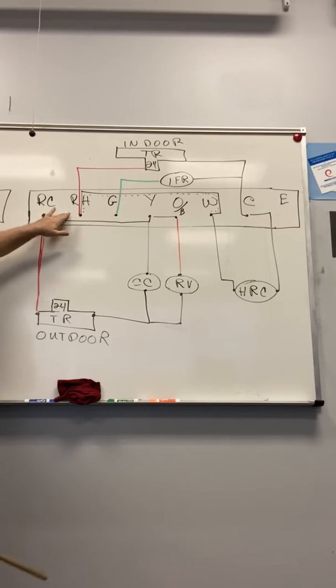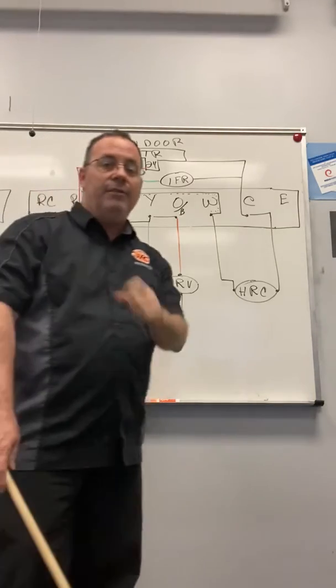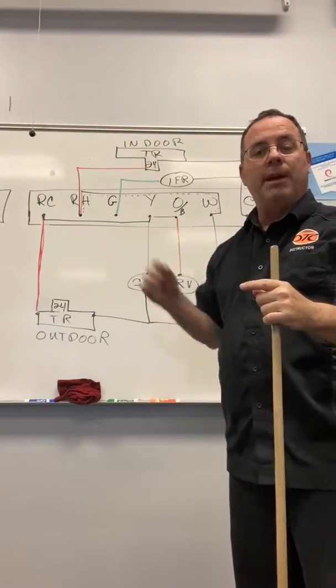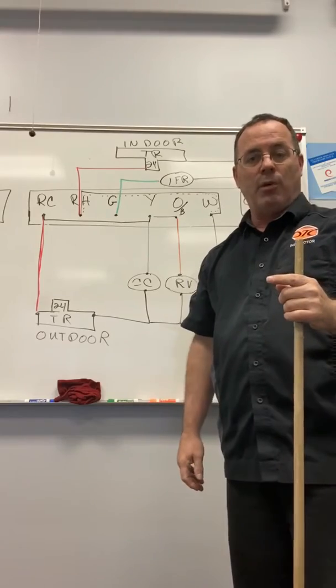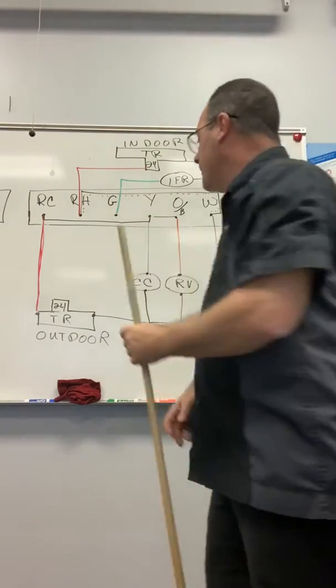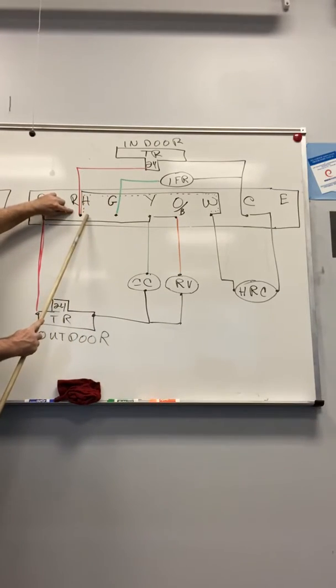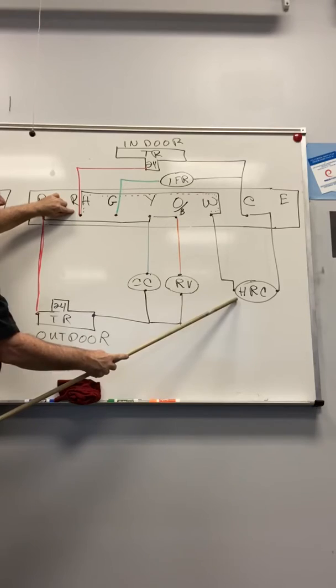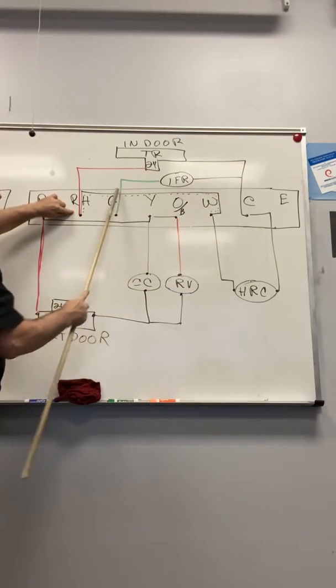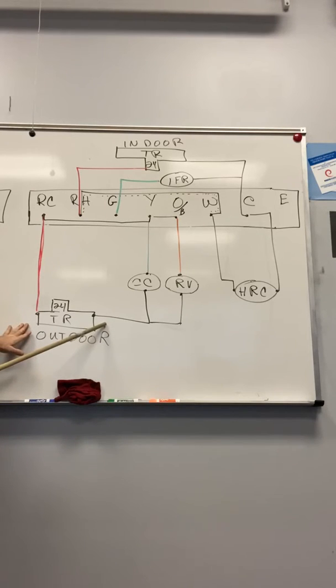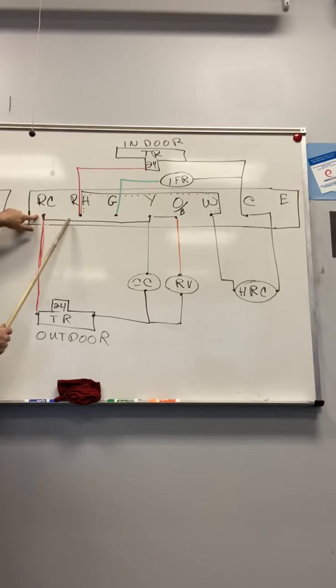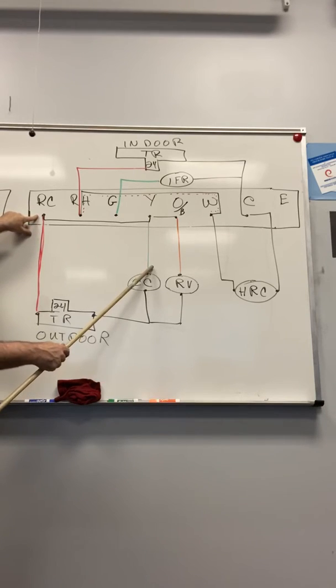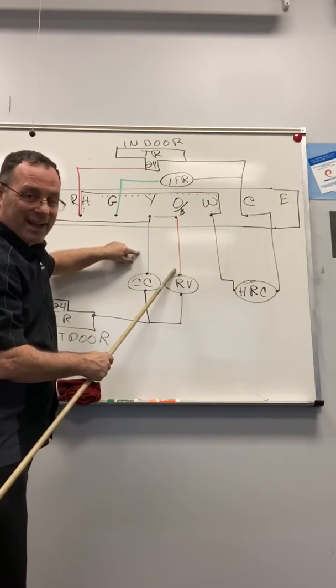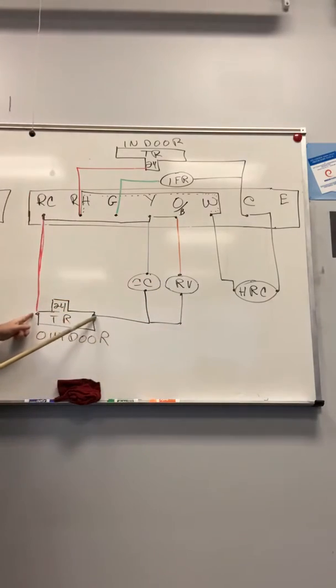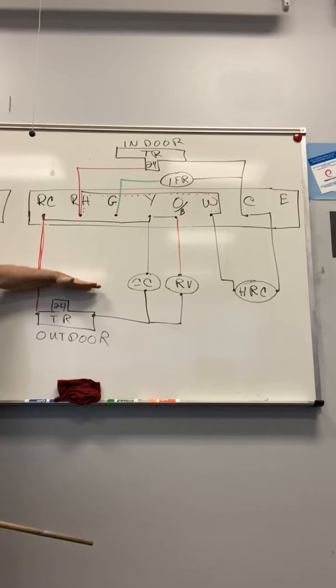So now we take the jumper that was on here off. If you have a dual transformer system and you open up that thermostat, you need to take that red wire jumper off between RH and RC. Now, my indoor will send power to heat, which will energize my heat relay coil through W, and there's my common and my blower. Notice the outdoor transformer now. One wire goes to RC, which will then energize what? My contactor coil, my reversing valve, and common goes back to that transformer.